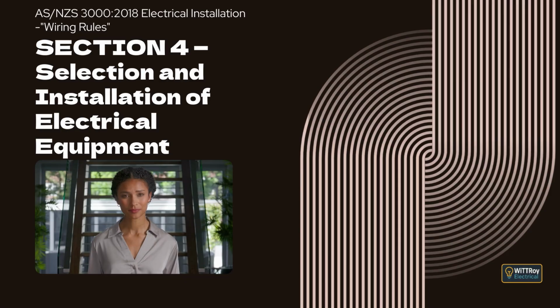Clause 4.20.4.2 MRL switchboards. Switchboards associated with motor room-less lifts must not be located in the lift shaft and must be readily accessible where they are remote from the main switchboard. Clause 4.20.4.3 Switchgear. Protective and control devices for motor room-less lifts must be located in a readily accessible position to allow safe operation, inspection, and maintenance.